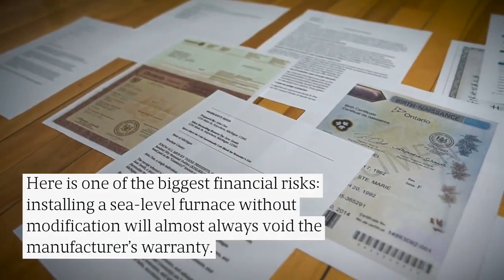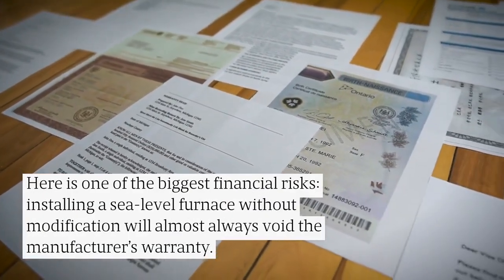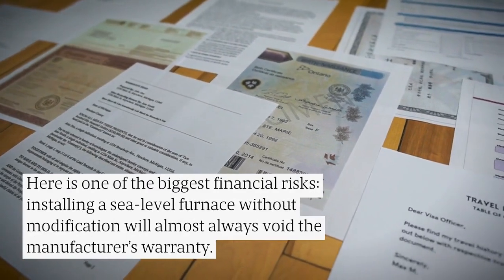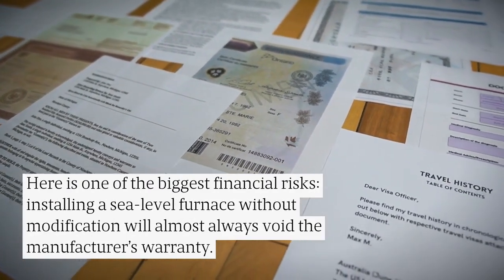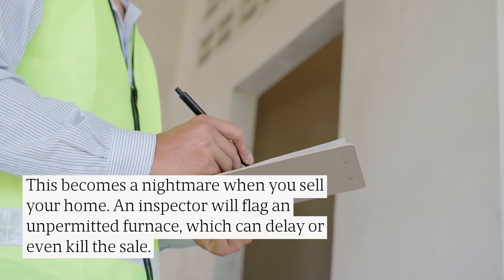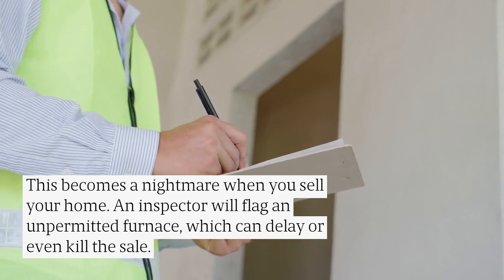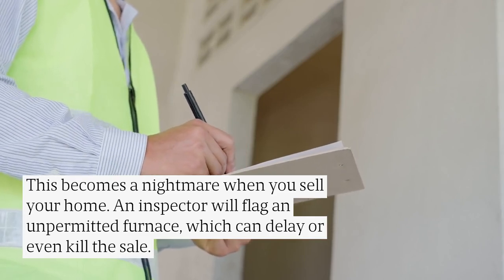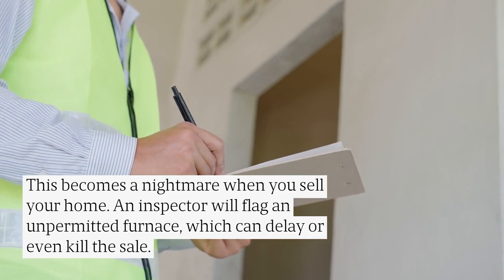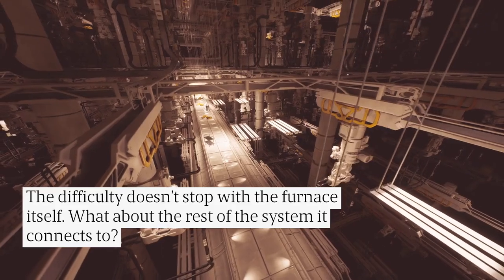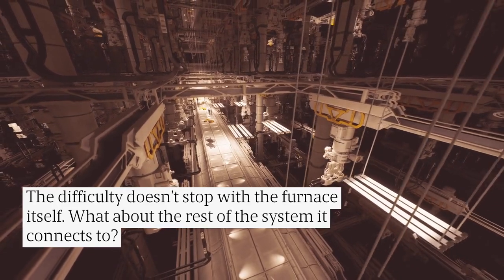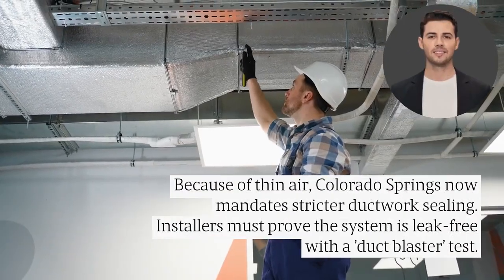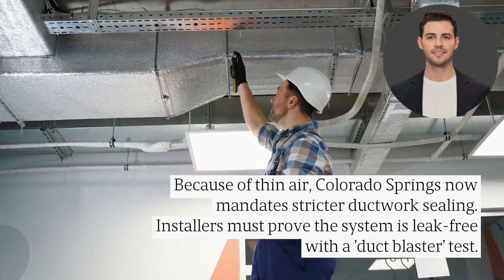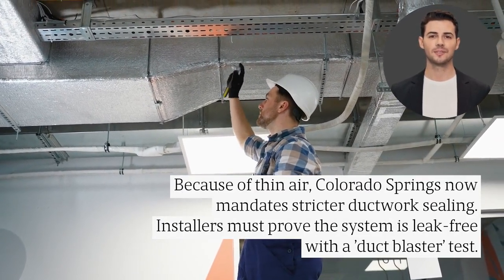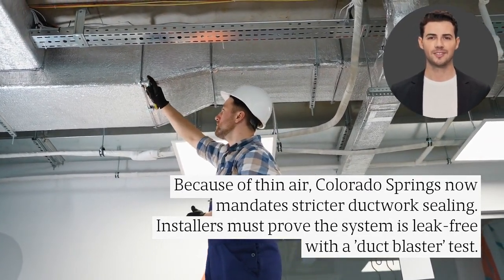Here is one of the biggest financial risks. Installing a sea-level furnace without modification will almost always void the manufacturer's warranty. This becomes a nightmare when you sell your home. An inspector will flag an unpermitted furnace, which can delay or even kill the sale. The difficulty doesn't stop with the furnace itself. What about the rest of the system it connects to? Because of thin air, Colorado Springs now mandates stricter ductwork sealing. Installers must prove the system is leak-free with a duct blaster test.